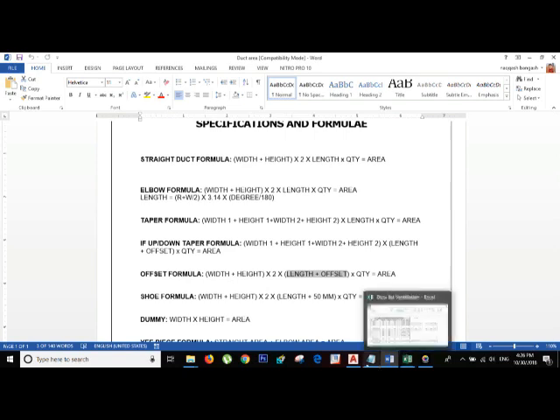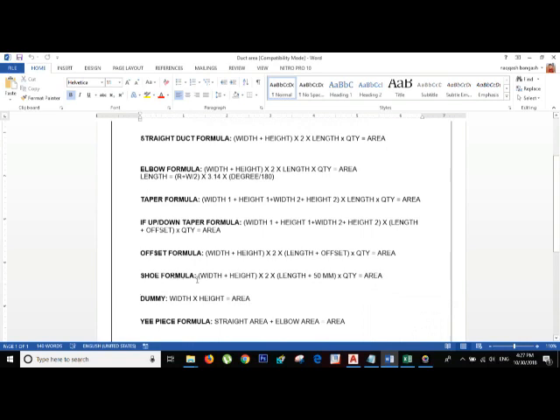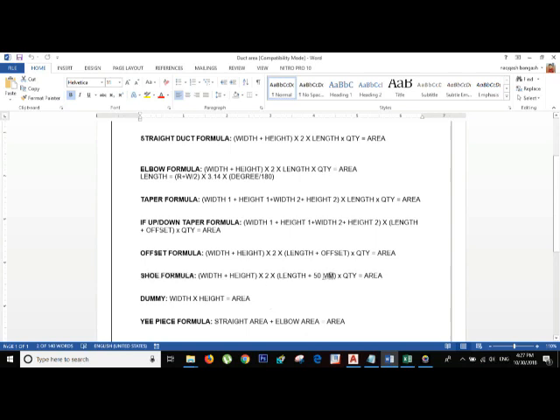Thank you for watching. For the shoe neck formula, it's the same as a straight duct: width plus height multiplied by two. But when calculating a shoe neck branch, you can see the 50 mm extra piece — just add 50 mm to the length when you calculate the area of the shoe neck. If there is a large quantity, multiply the area by quantity to get the total area.